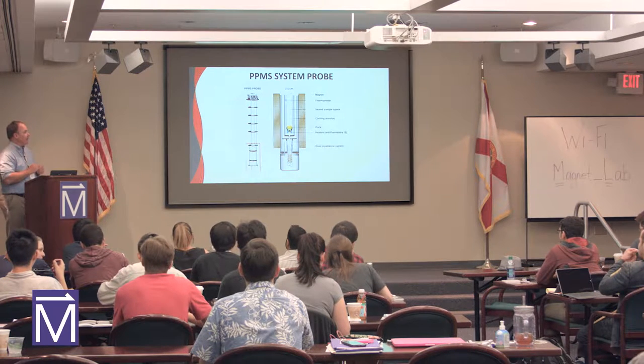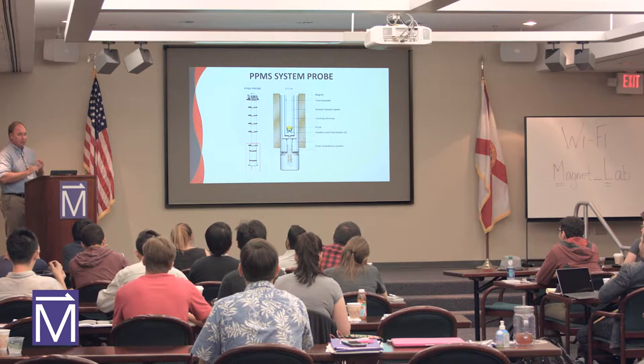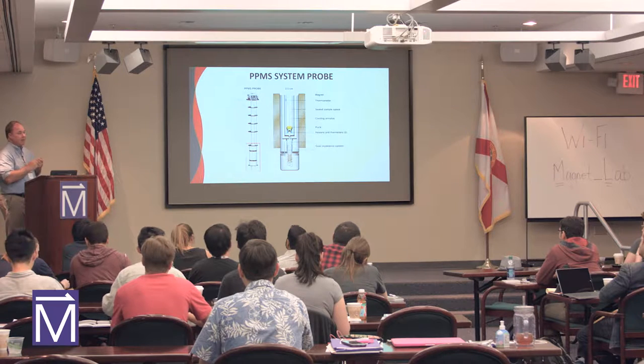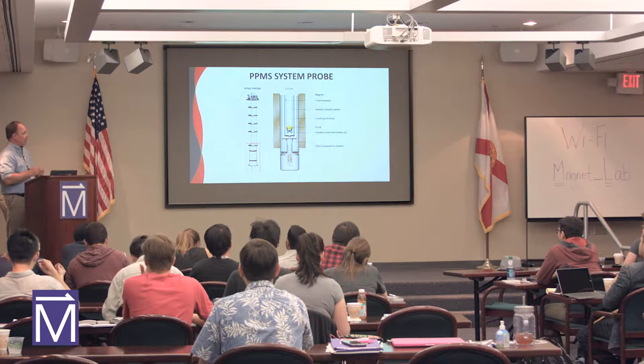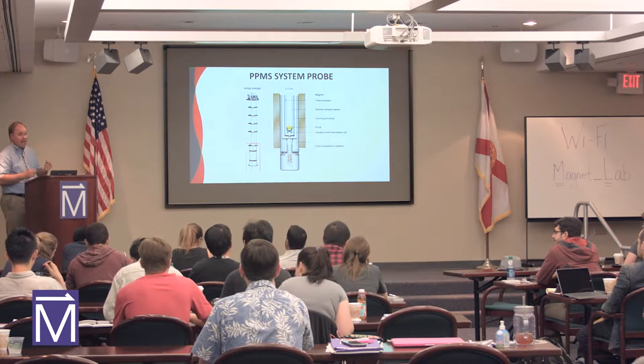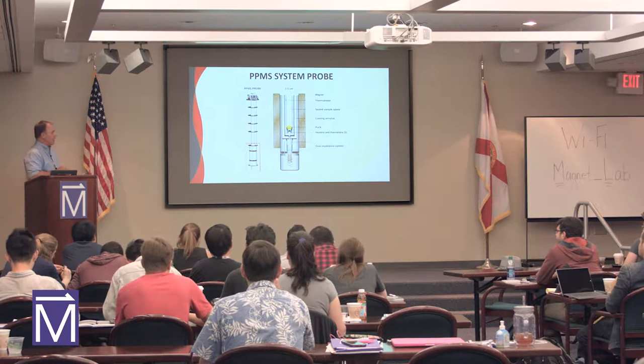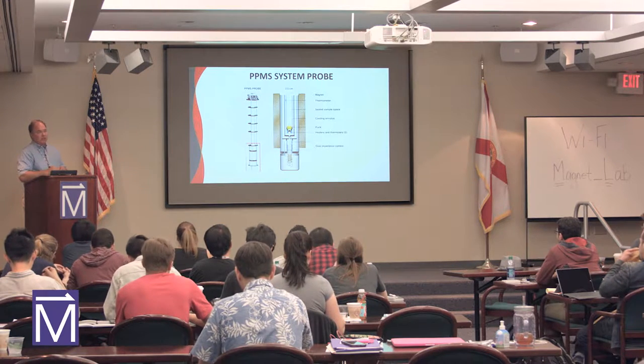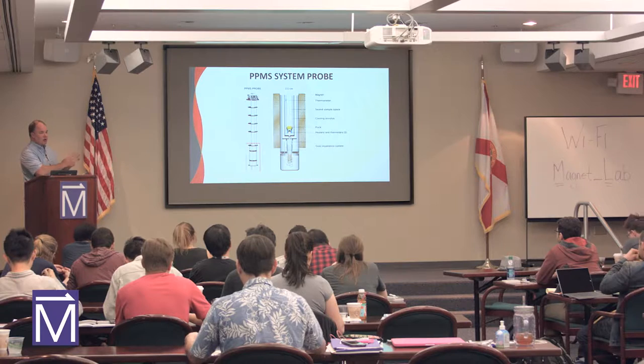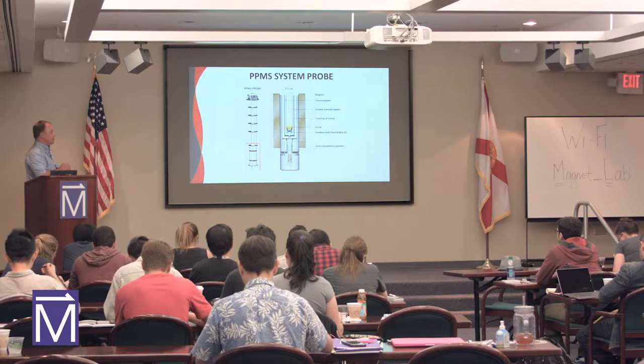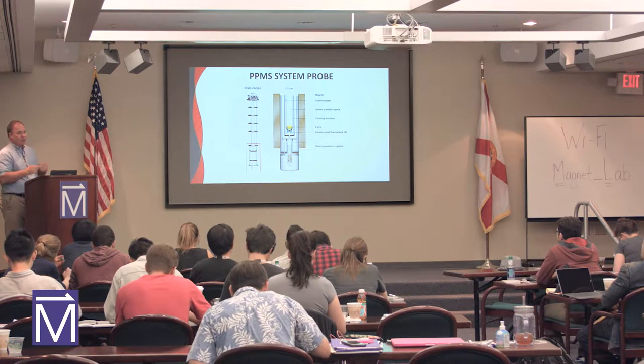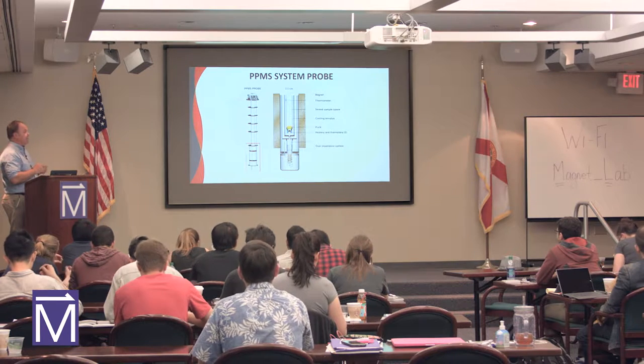So the important thing that we want to provide is good temperature control and good temperature stability. Your sample is at the correct temperature, or the sample space is at the correct temperature, and then the magnetic field, right? So you can control those, and we have the electronics in the rack that control those two factors and the control system that controls the PID.